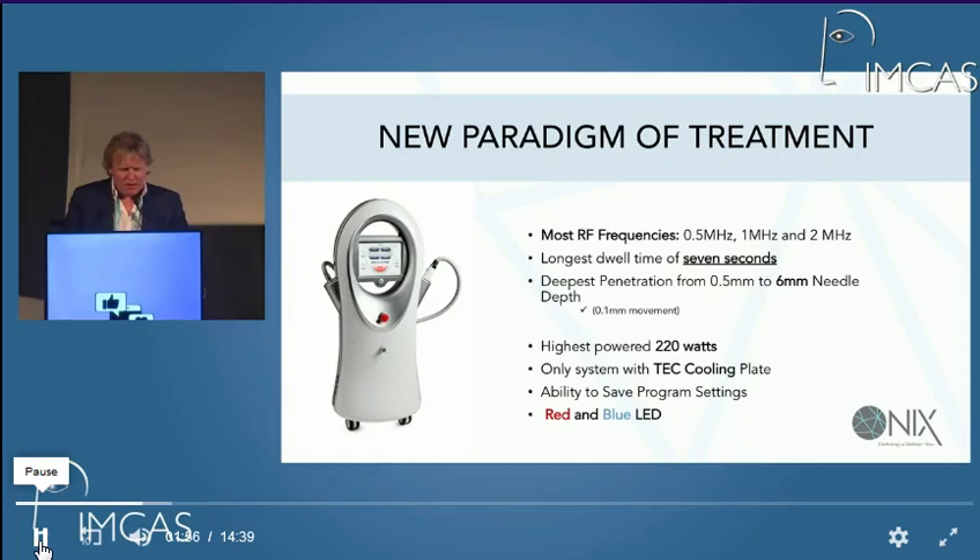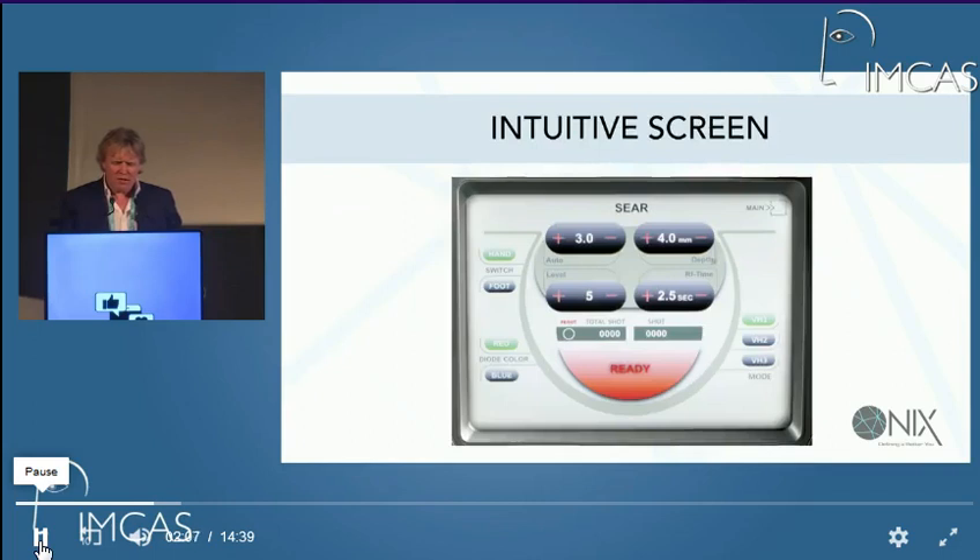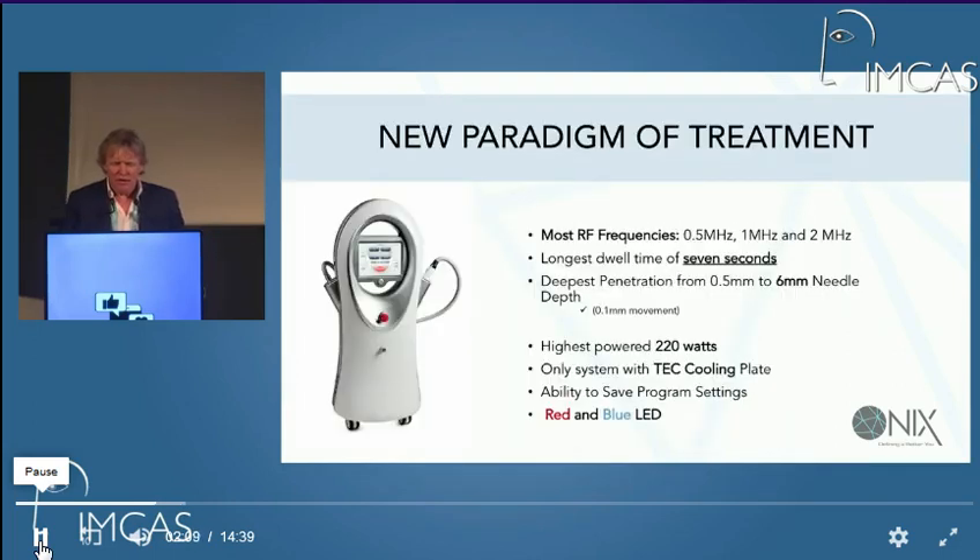What's different about Onix is that it uses different RF frequencies — a bit like radio surgery, using coag and cutting heads. The machine gives different patterns at 0.5 MHz, 1 MHz, and 2 MHz. It's got a dwell time of quite a long time — 7 seconds.